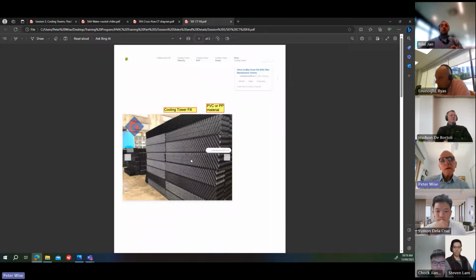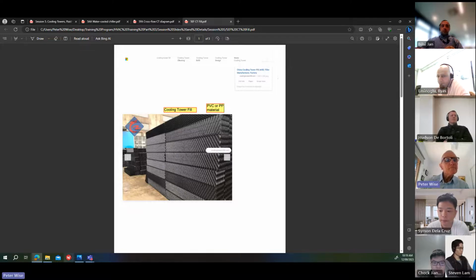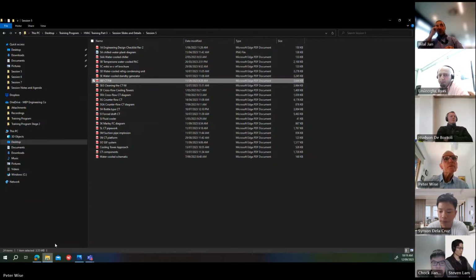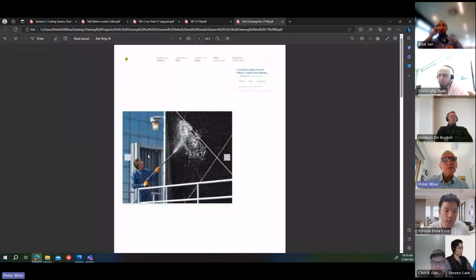These are fill elements ready for shipping out. So it's a PVC or polypropylene material. There are other materials, but they're the most common. And to see it in situ, got a picture of a fellow here cleaning the fill with a high pressure spray. So that needs to be done on a regular basis, because you will get scale forming on the fill.